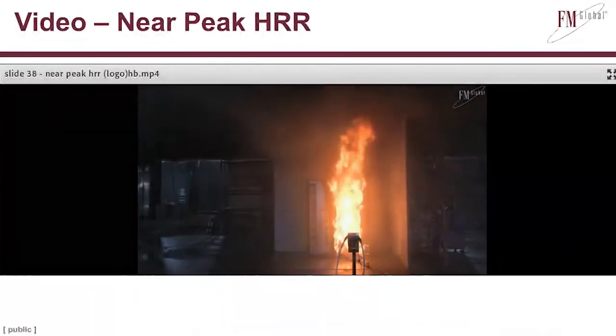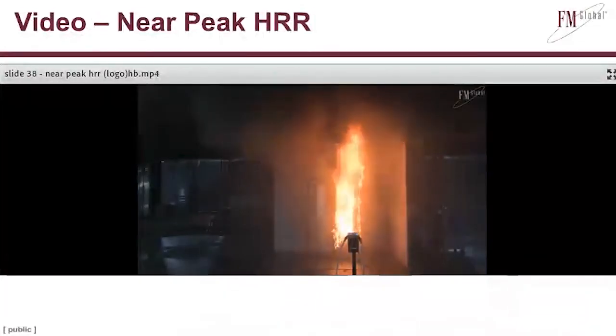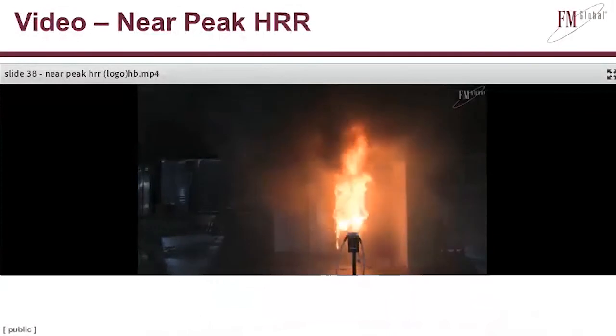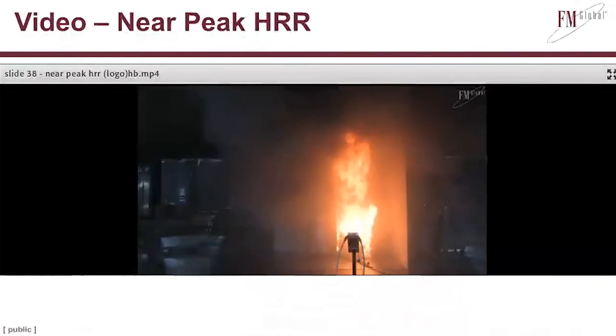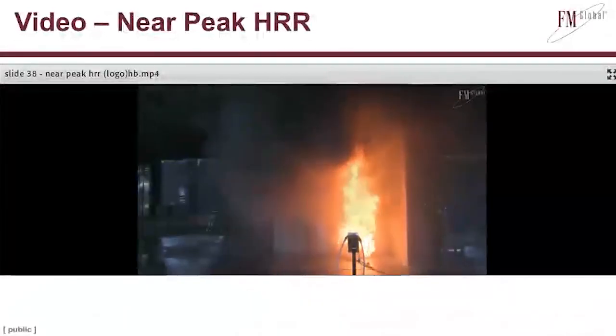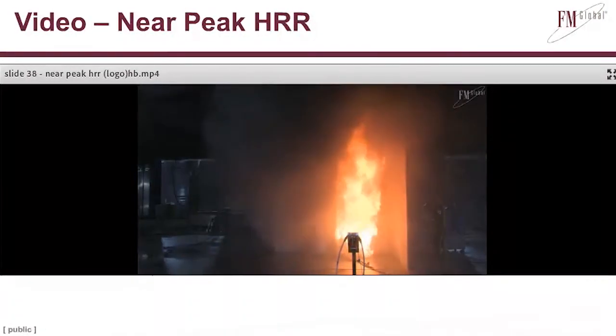Okay, so now you can see a very large fire developing. We're going to start to see spreading, where the fire starts to actually spread horizontally and gets closer to the walls. It also reaches the ceiling and starts to spread horizontally across the ceiling. Again, I was astounded at this point that we didn't have ignition of our target rack, which is full of batteries that can go into thermal runaway due to heating, and you have a fire of this magnitude literally inches away.